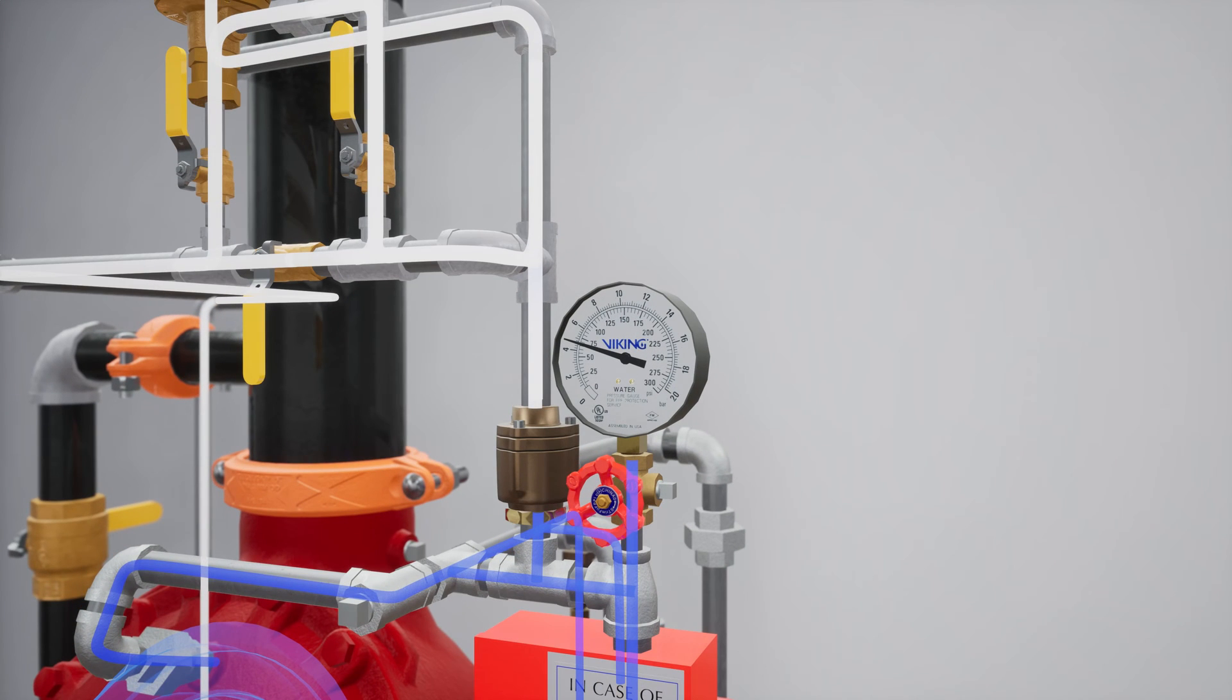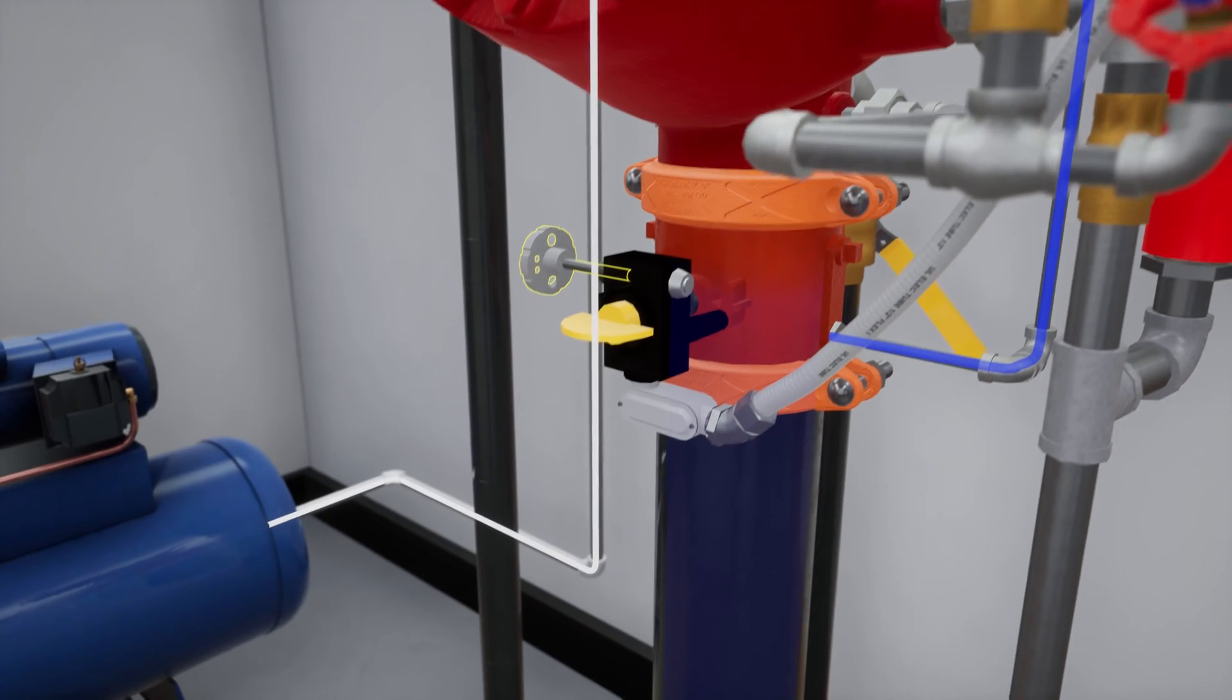Next, partially open the flow test valve. Once water pressure has been established in the prime chamber, slightly open the water supply control valve and begin introducing water into the system.